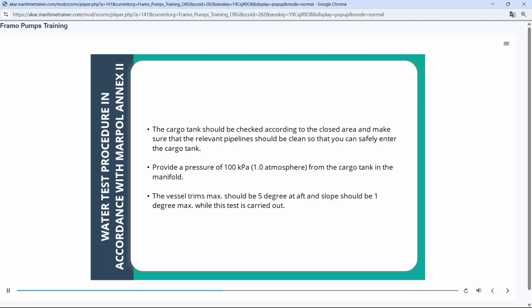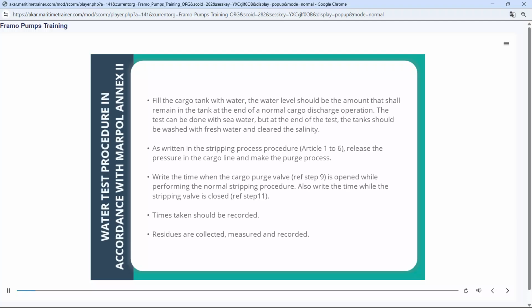Provide a pressure of 100 kilopascals, 1.0 atmosphere, from the cargo tank in the manifold. The vessel trim's max should be 5 degrees at aft and slope should be 1 degree max. While this test is carried out, fill the cargo tank with water. The water level should be the amount that shall remain in the tank at the end of a normal cargo discharge operation. The test can be done with seawater, but at the end of the test, the tanks should be washed with fresh water and the salinity cleared.